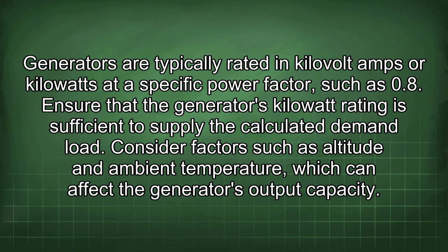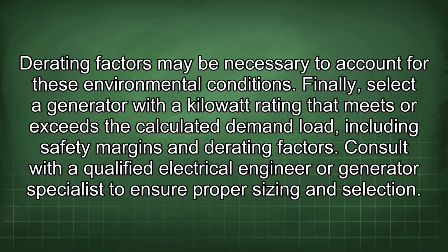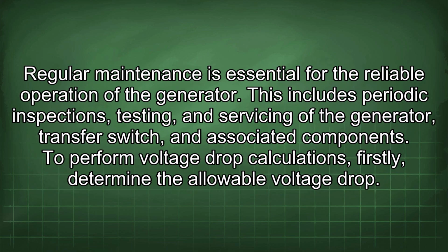Consider factors such as altitude and ambient temperature, which can affect the generator's output capacity. Derating factors may be necessary to account for these environmental conditions. Finally, select a generator with a kilowatt rating that meets or exceeds the calculated demand load, including safety margins and derating factors. Consult with a qualified electrical engineer or generator specialist to ensure proper sizing and selection. Regular maintenance is essential for the reliable operation of the generator. This includes periodic inspections, testing, and servicing of the generator, transfer switch, and associated components.